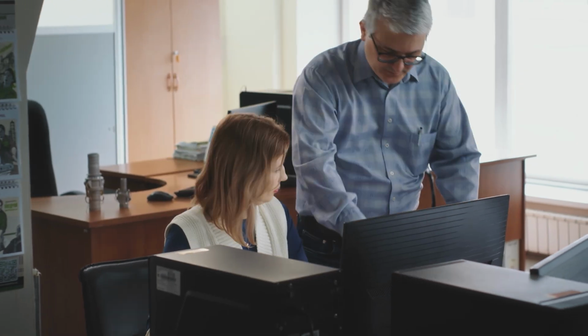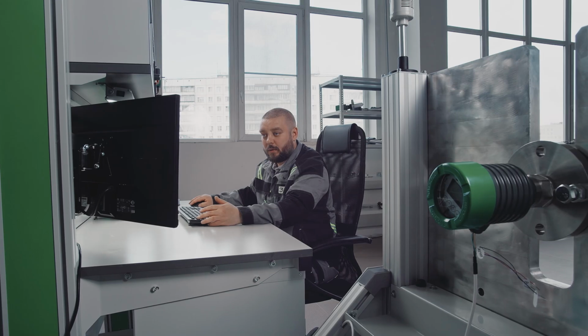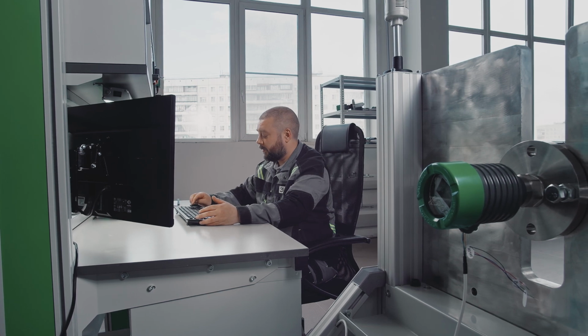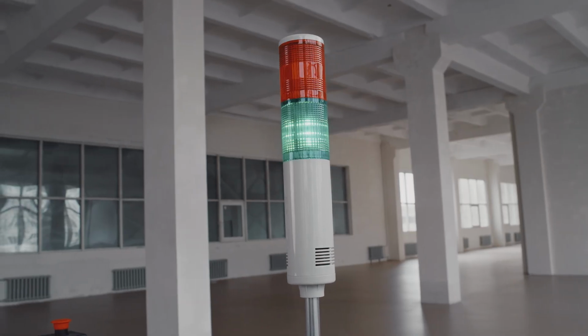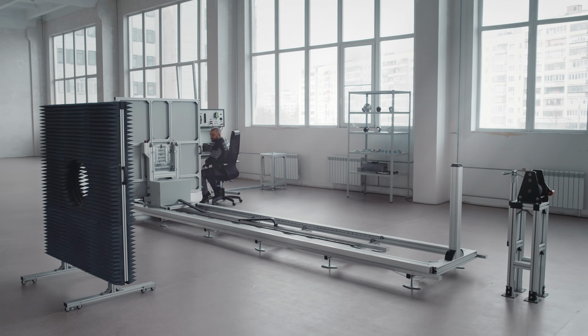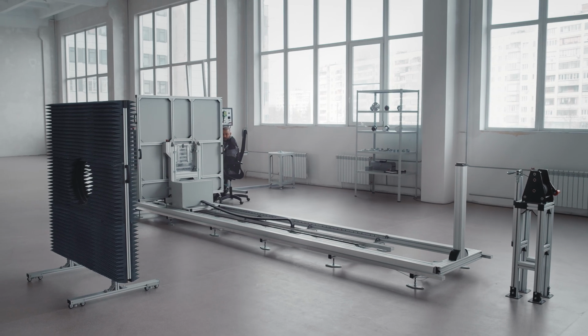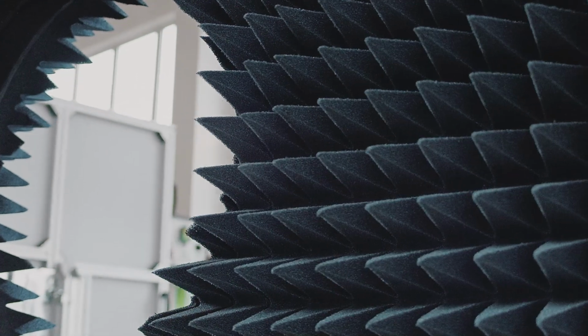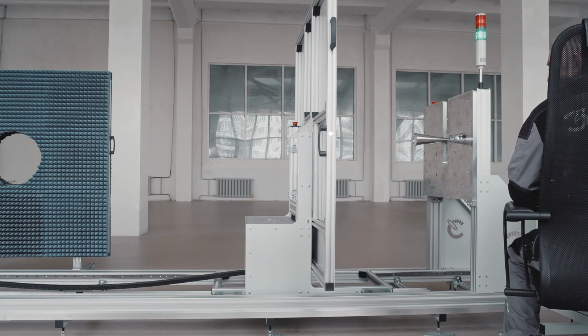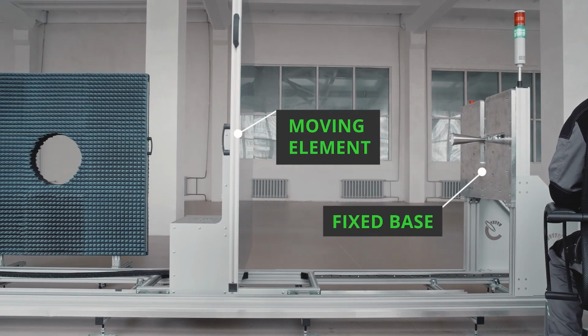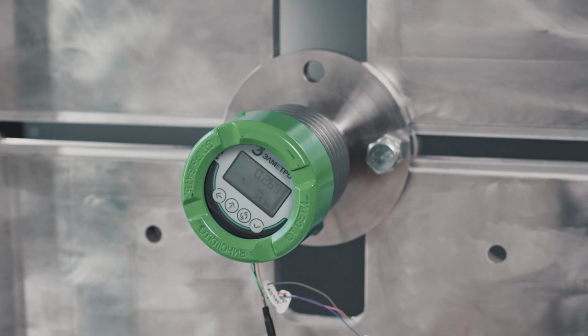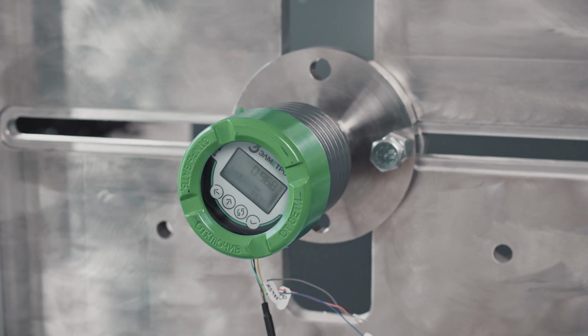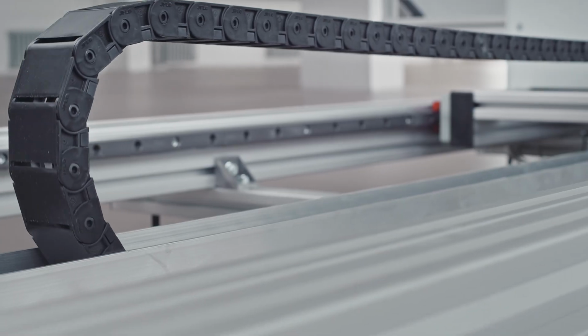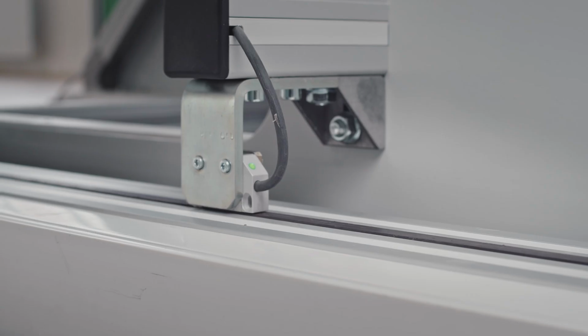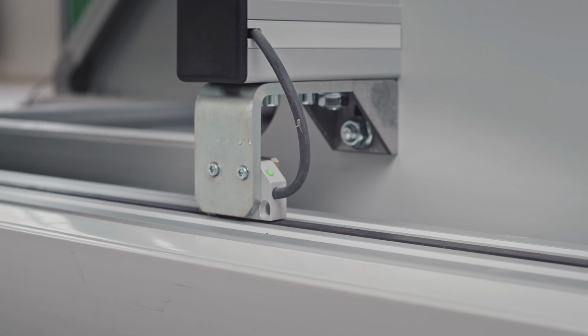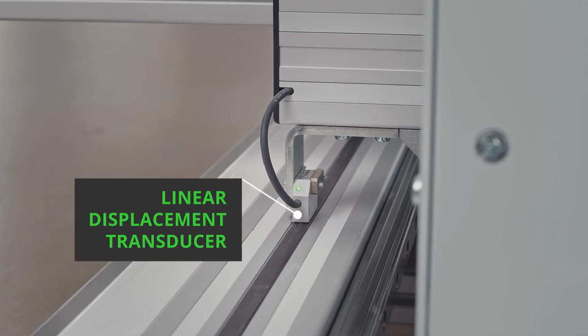They select the optimum configuration of the bench, taking into account the ergonomics and convenience for the operator, laboratory parameters. Simulation of the change in the level is performed in the horizontal plane by displacement of the moving element with reflective surface against the fixed base on which the verified instrument is placed. The distance simulated by the bench is set using the standard linear displacement transducer.